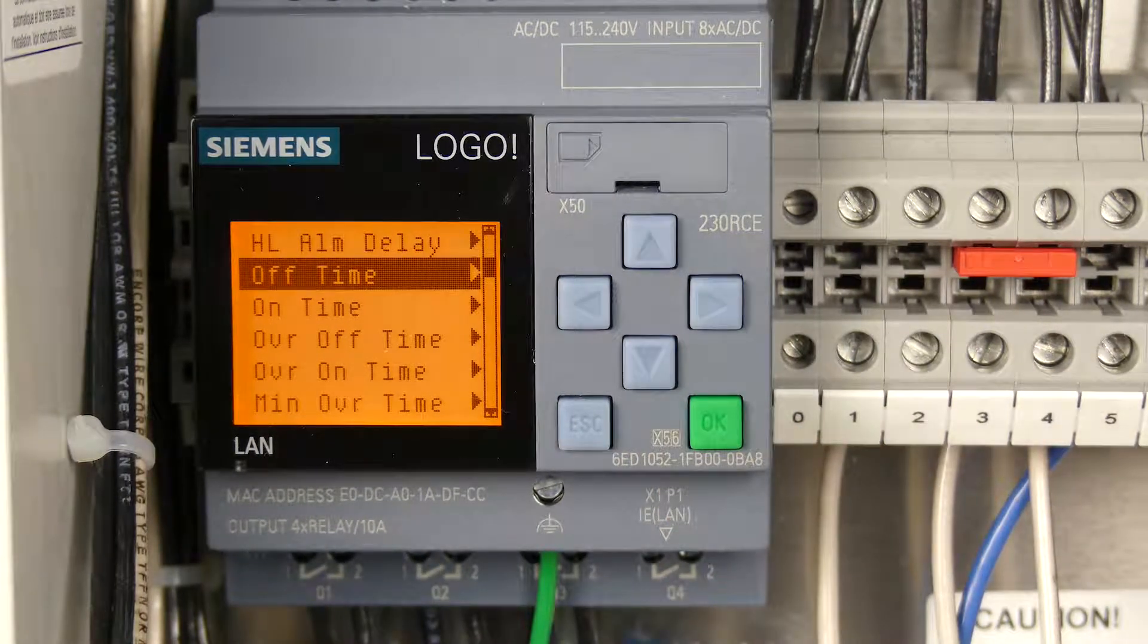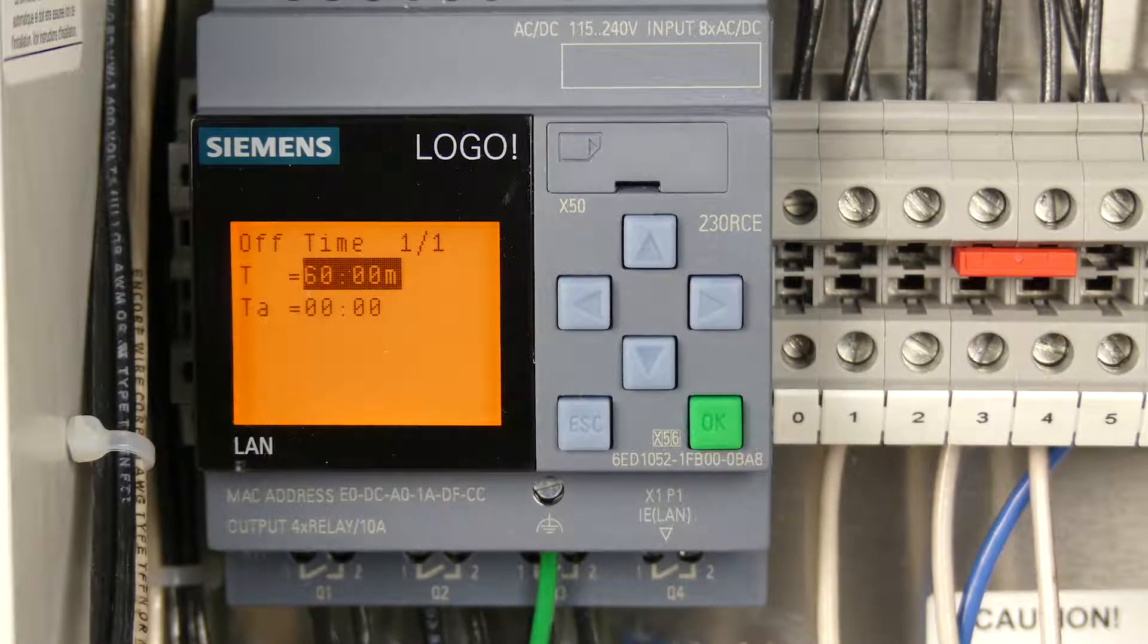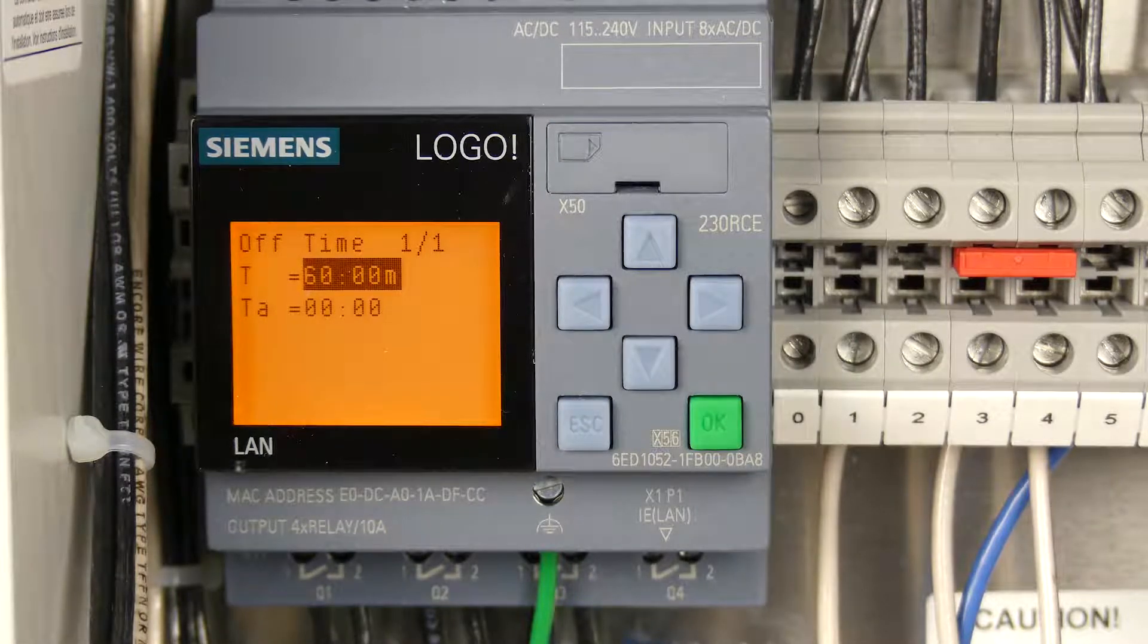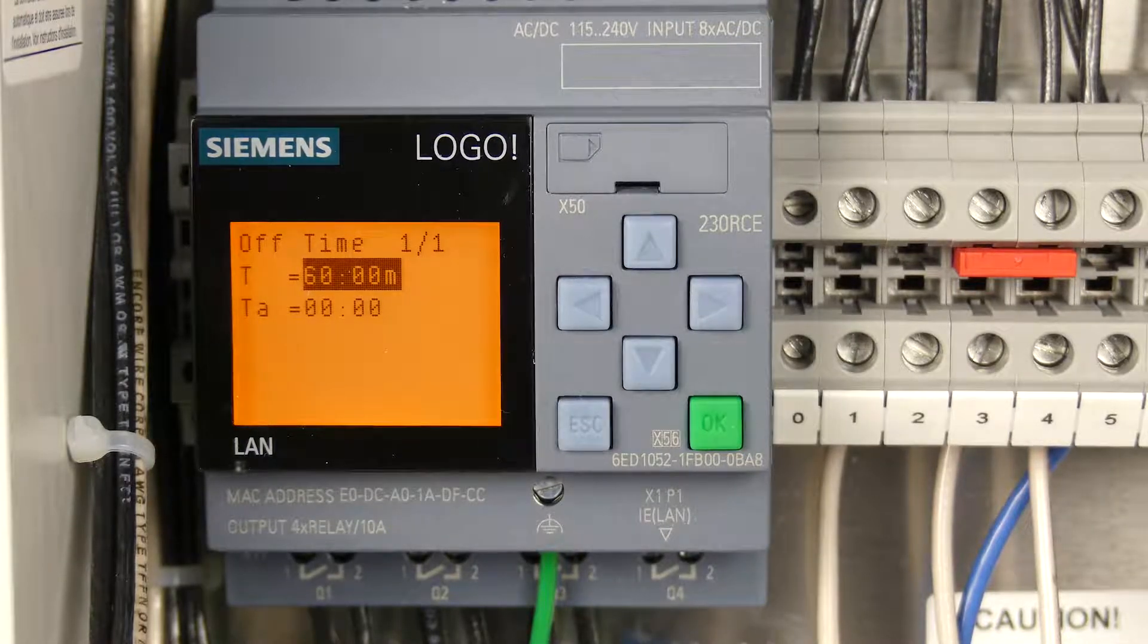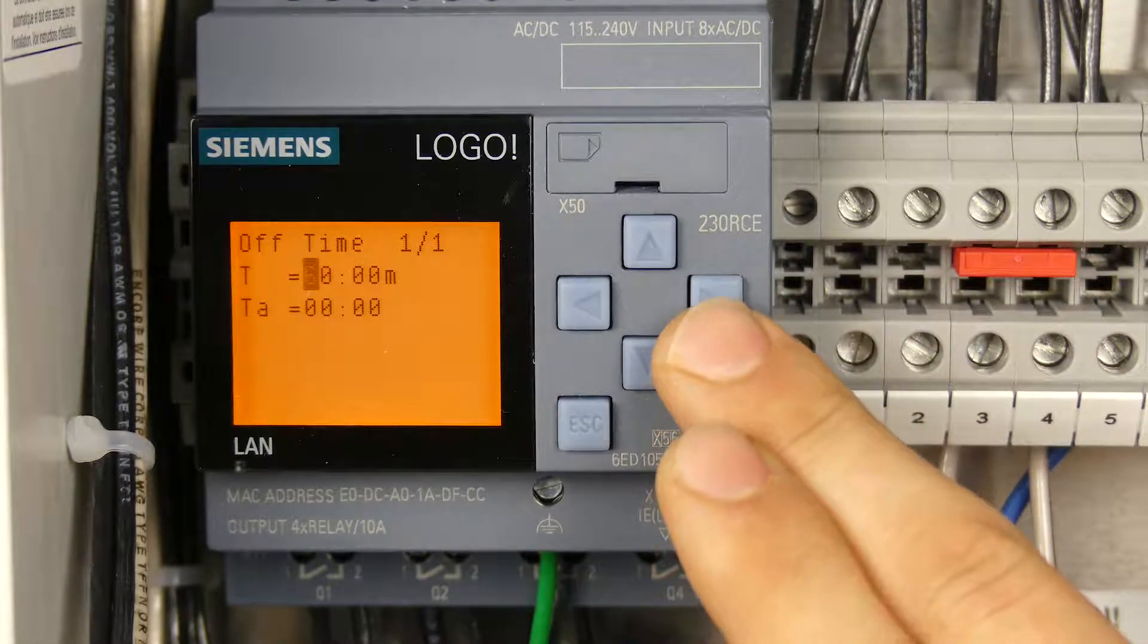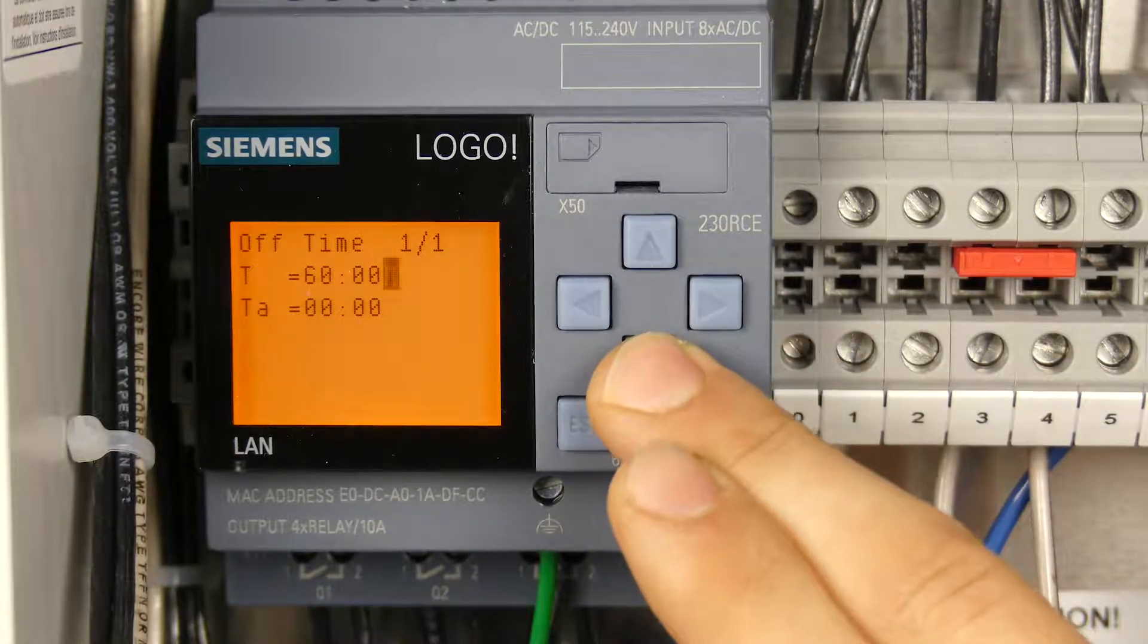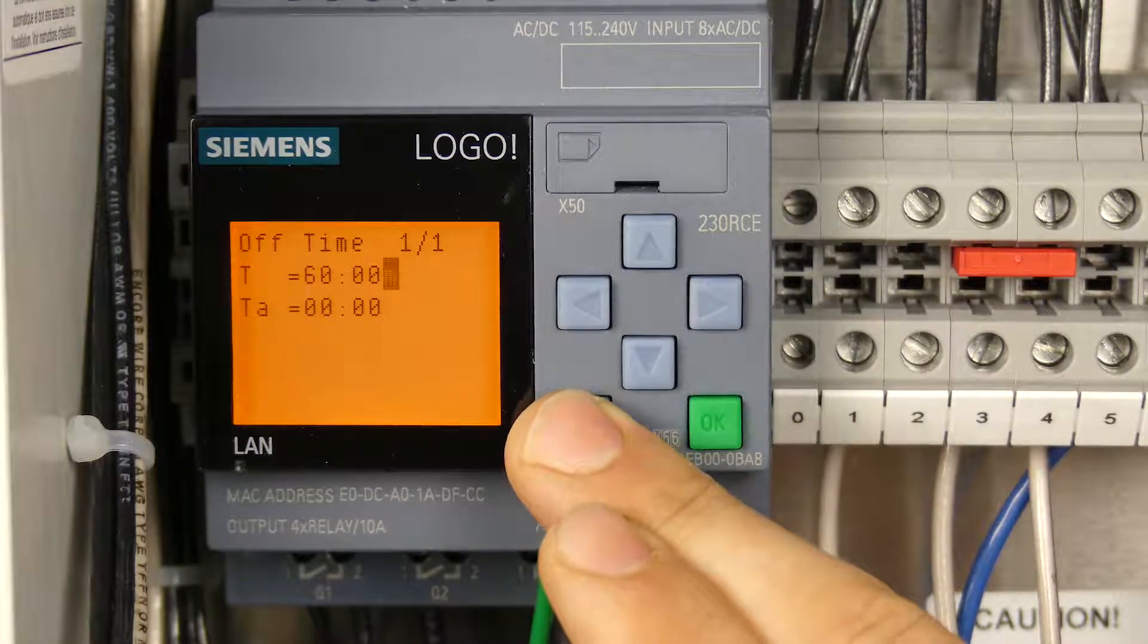Let's talk about the off timer. The off time on these panels is how long the system stays off until it cycles the pump. By off time, we're counting down the minutes until we reach the minimum pump run time, and then the pump cycles and this clock starts over again. This one's adjustable where you press OK to enter edit mode and you move left and right to adjust your minutes accordingly. You can change this from minutes to hours to seconds depending on your specific application.